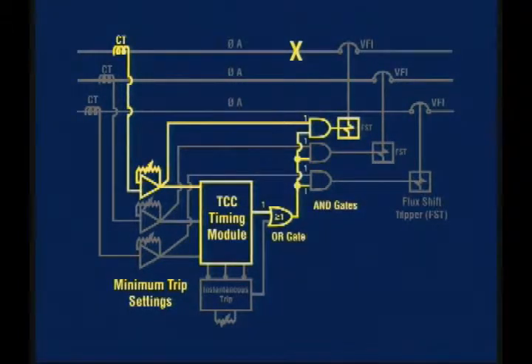At the completion of the time delay, the trip circuit generates a pulse which actuates the flux shift tripper, releasing the switchgear operating mechanism to open the main contacts. An assortment of field-replaceable TCC modules is available. Each provides a fixed time current curve characteristic.